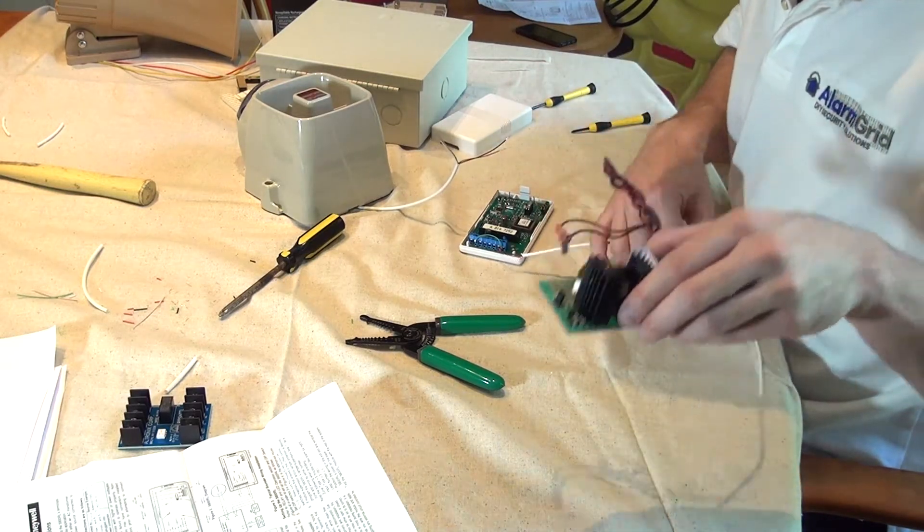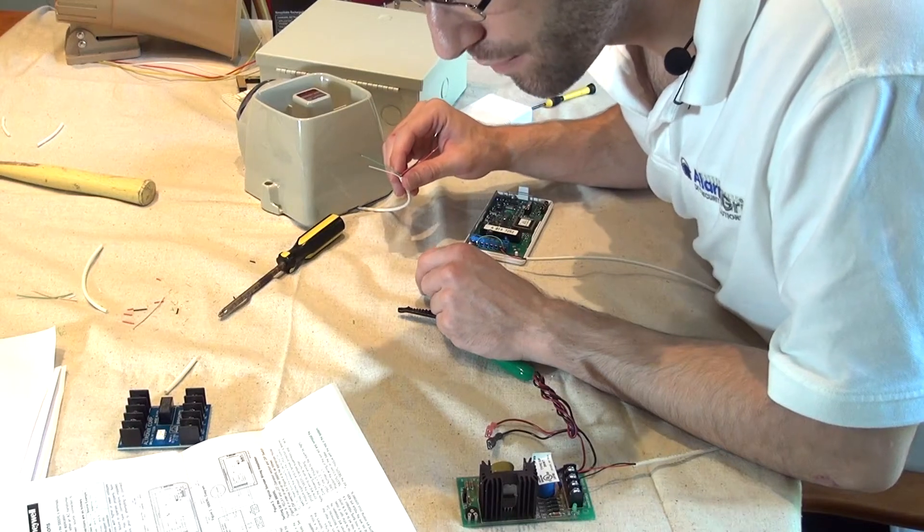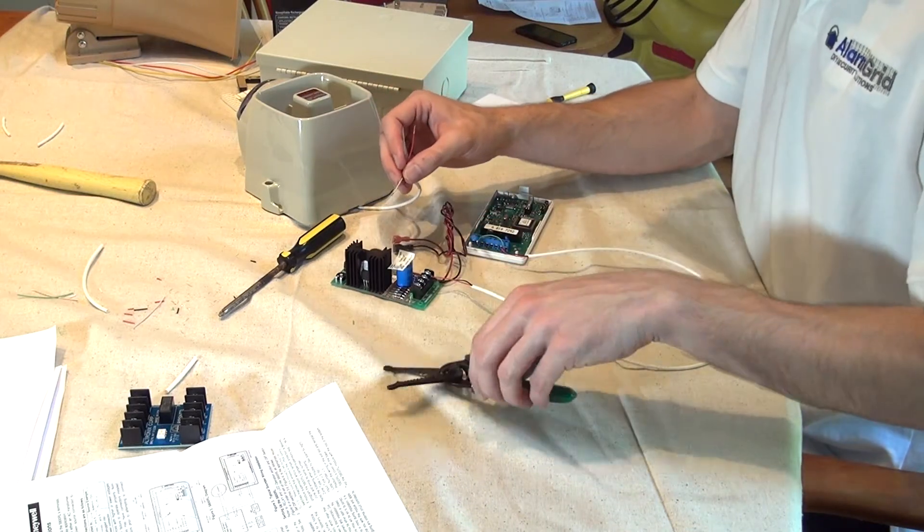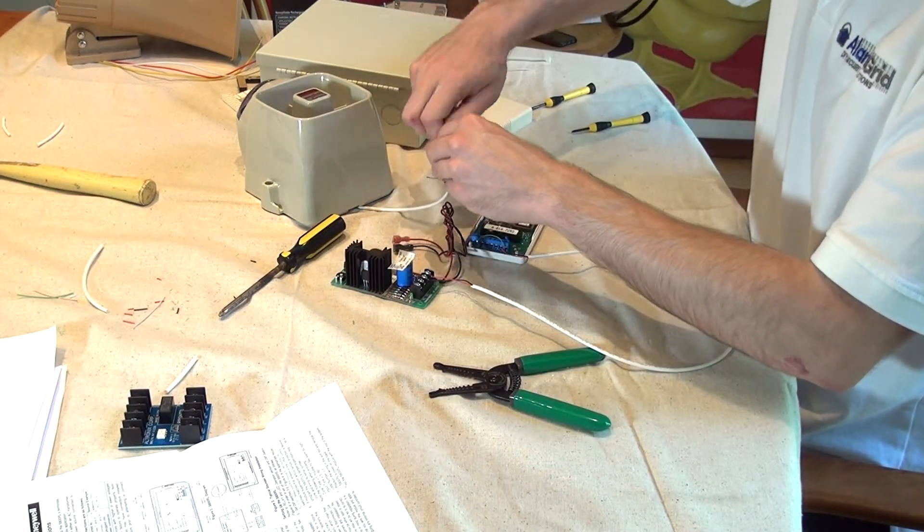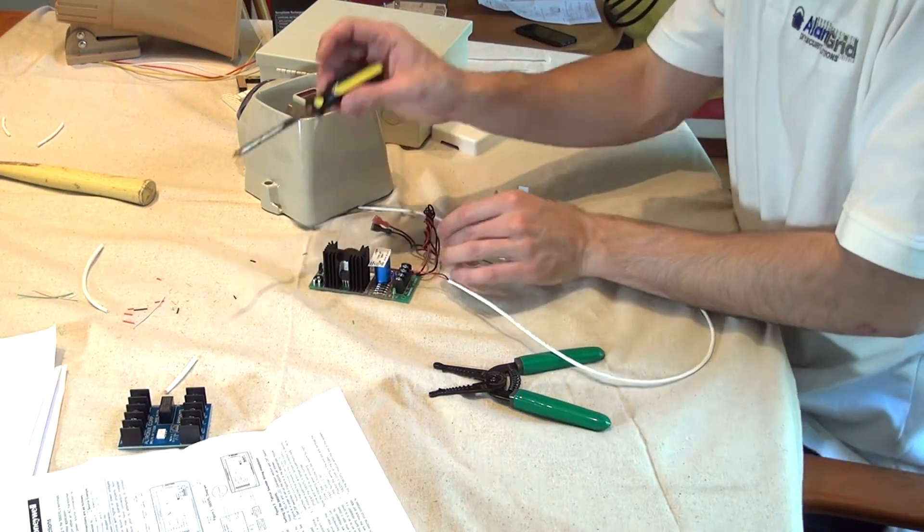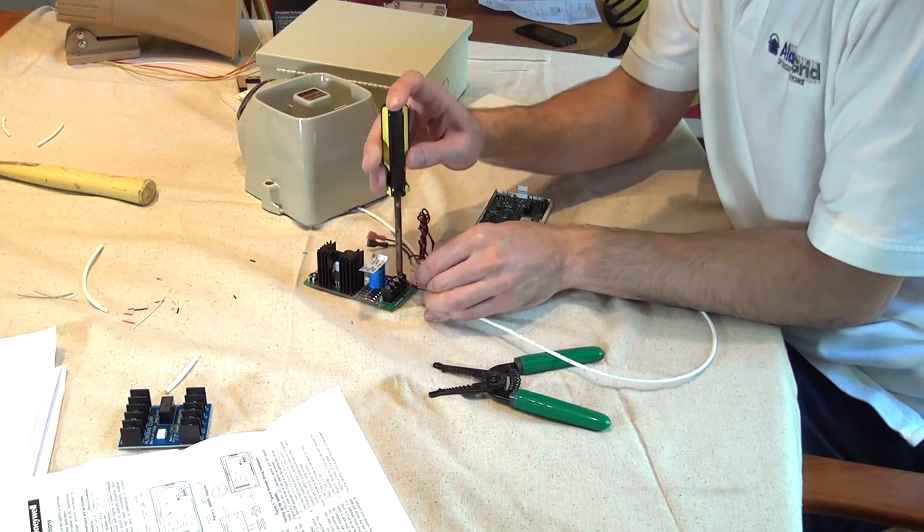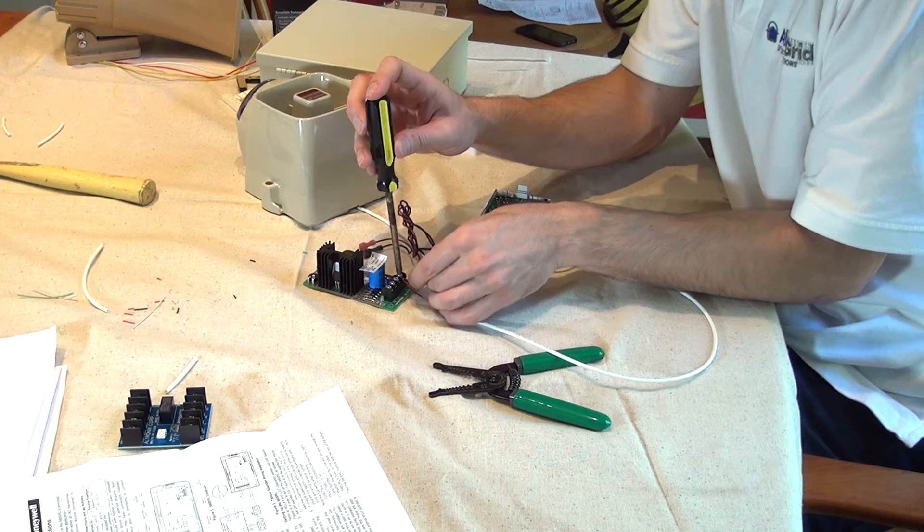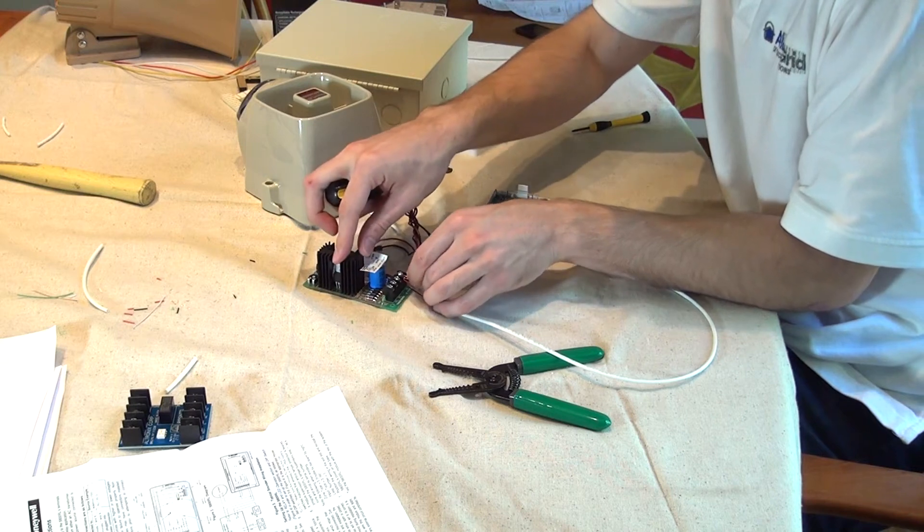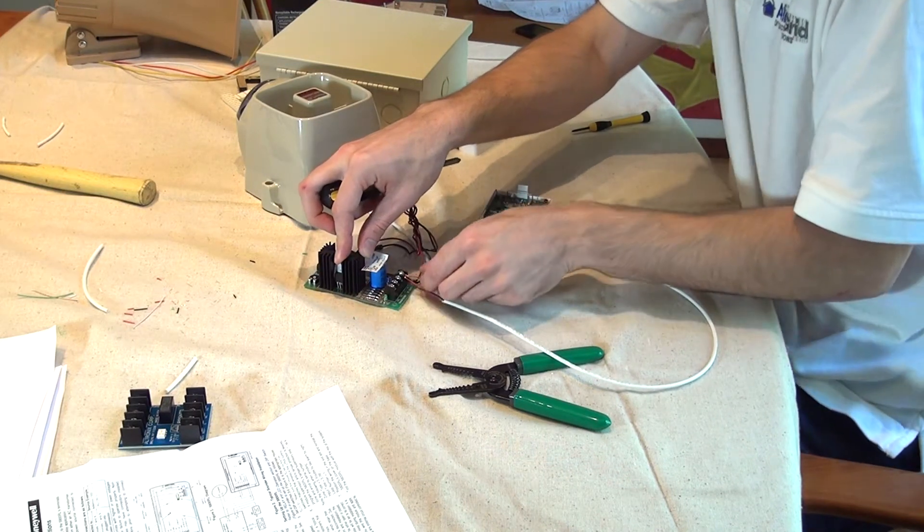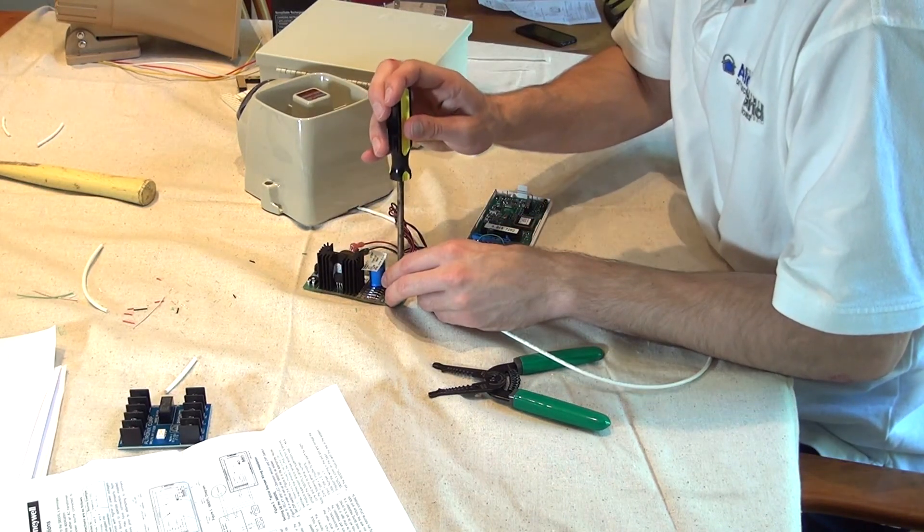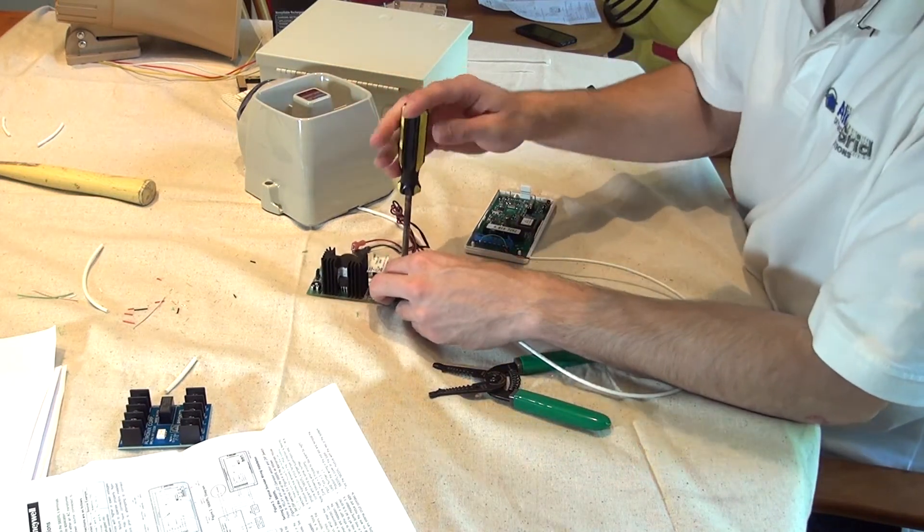These connections, we're going to go positive to our DC output on our power supply. So we're going to twist together the black and the green, and we're going to land it underneath the same terminal that's feeding our DC output to our relay module. So we're going to have three connections going here, screw it down tight. That's our positive side.